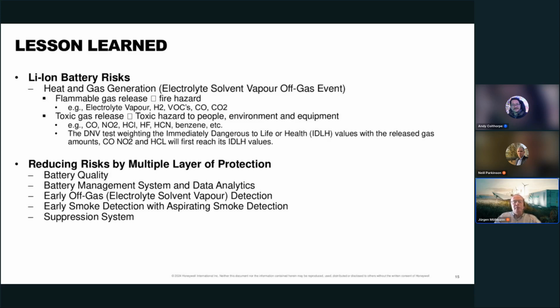Therefore, we are looking at different layers of protection. There is not only one solution for battery safety. As I said before, by nature there is a risk and we have to work with this and reduce the risk as much as we can. Going back to the oil and gas industry, it's common to have a risk assessment and risk mitigation by looking at different layers of protection. In this case, again: battery quality, battery management system, data analytics, early off-gas detection, early smoke detection, and suppression if we still have a fire, either from a battery or from other sources like cables.